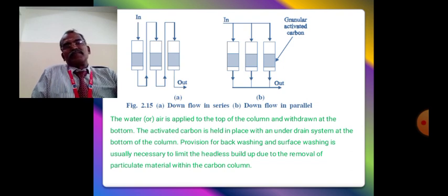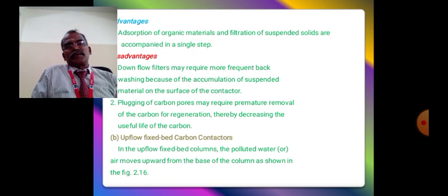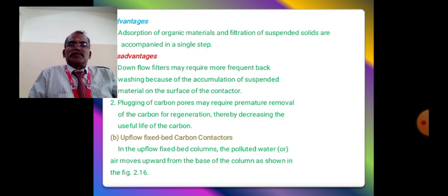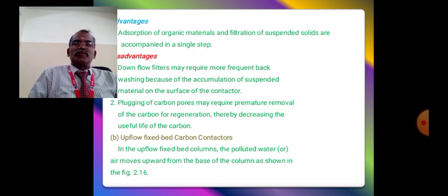Next, let me see the upflow method. But before that, the disadvantages of the downflow method. There are two. First, downflow filters may require more frequent backwashing because of the accumulation of suspended materials.